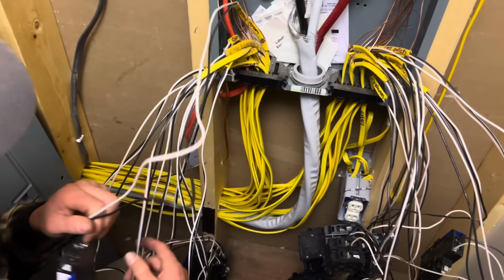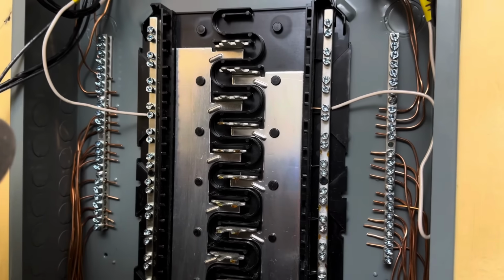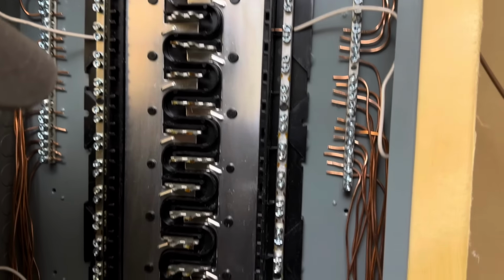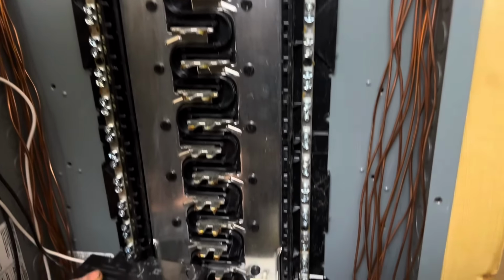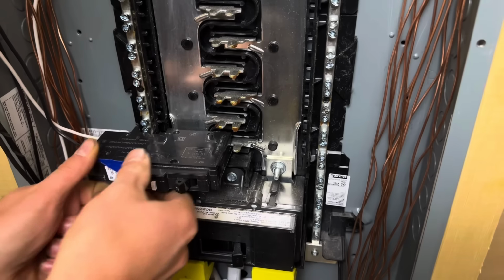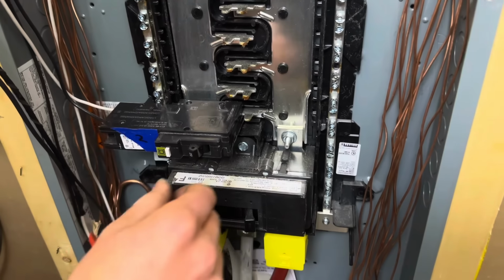This is Ethan. He's an electrician as well as a plumber. So what he's doing is we had to add these two ground bars. There's a ground bar and there's one. We had to add those, and then all the neutrals have to go on here. It wasn't quite set up properly the way the electrician had it set, so we are getting it figured out. Oops. There we go. And Ethan is very organized, so he labeled everything.